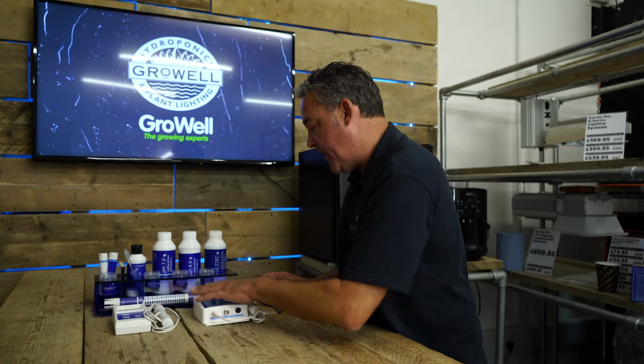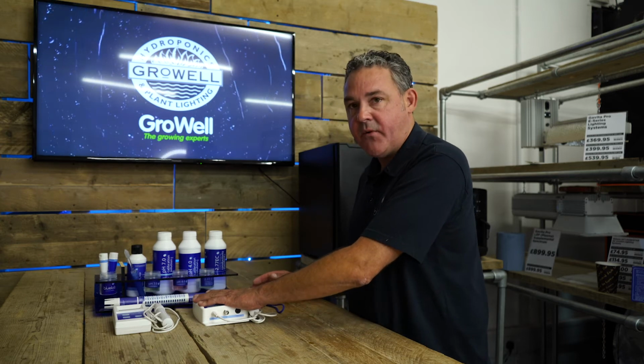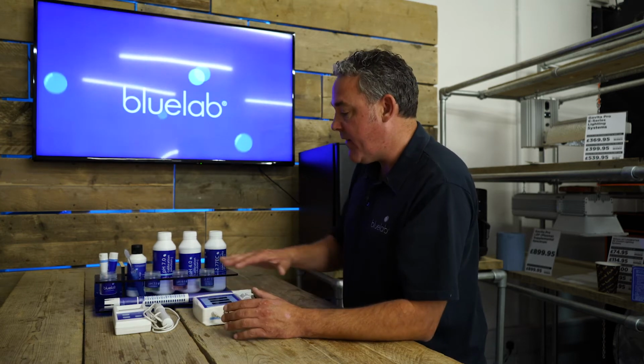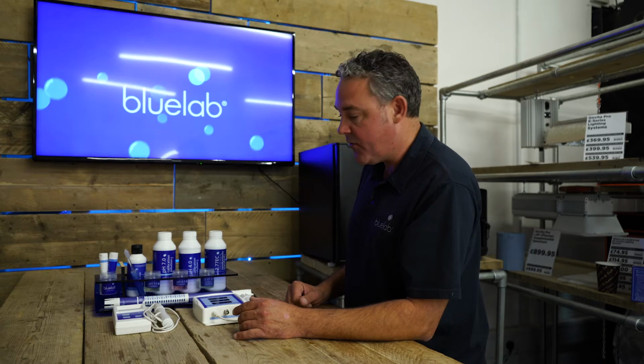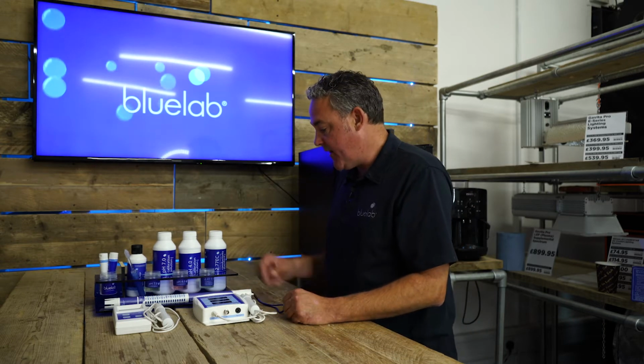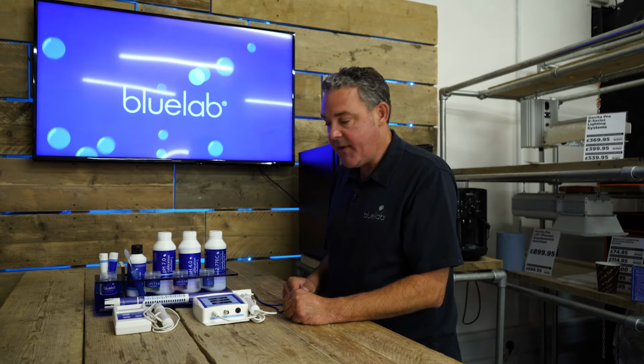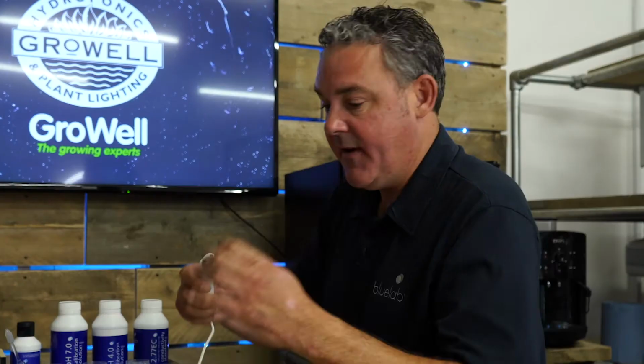With a digital reading, that can read anywhere between 2.7 and 2.9. That's within specification. All of our EC meters are accurate to 0.1 plus or minus. So all you need to do is regularly test it in 2.77. We recommend every month. And if it reads low, you need to clean it. Take this off for cleaning.